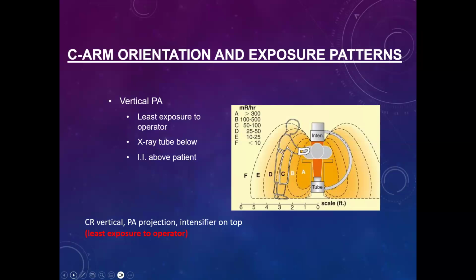All right, so here you see at the bottom, it says least exposure to the operator. You notice that the image intensifier is on top and the X-ray tube is on the bottom, okay? This is important for cath lab and OR techs. They should wear lead aprons, thyroid shields, perhaps lead gloves, depending on where they are within the field, and/or lead glasses. You can get prescription lead glasses to wear. Now, this configuration again, X-ray tube at the bottom, image receptor at the top, is the least exposure to the technologist, okay? Again, this is a definite registry question. You can count on seeing one of these pictures.